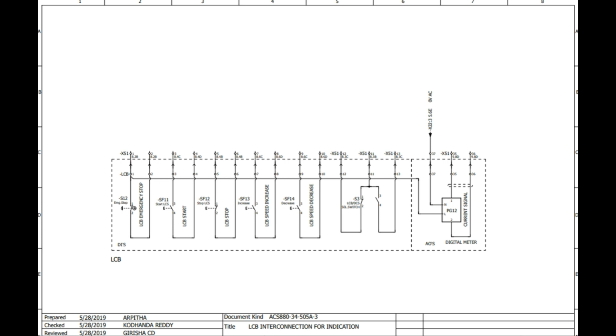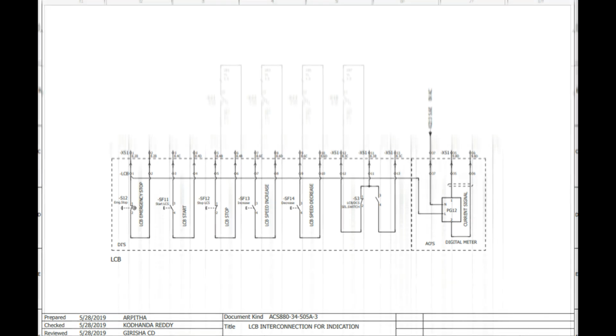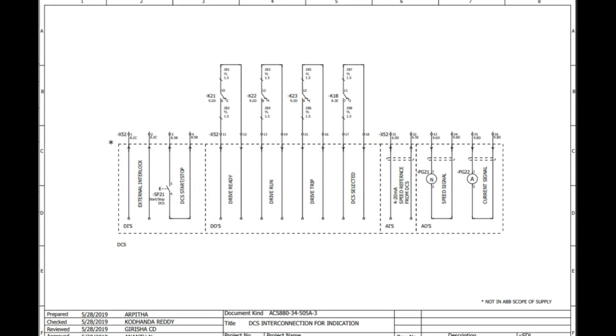We have to keep these held; I mean for these two, speed increase and decrease, we have to keep the button held. But the first three are for one time: the emergency button is pressed one time, the start button is pressed one time, the stop button is pressed once. Then X51 again, it is 11 and 12, and this is for selection, whether the system has to work from LCS or PLC/DCS. So 11 is common, 12 is for LCS, and 13 is for DCS. And lastly it is for the digital meter current signal. If required we will use it, if not we can skip it.